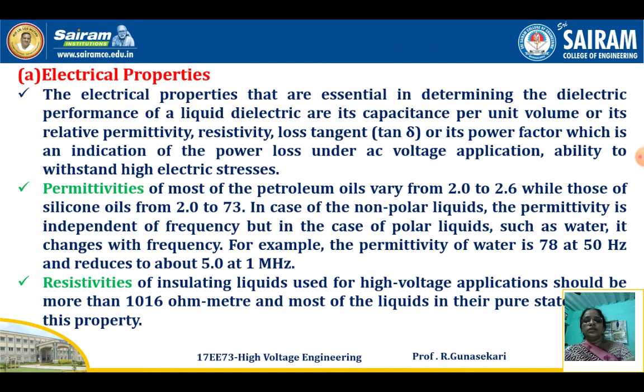Then resistivities. The resistivity of the insulating liquid dielectrics used for high voltage applications should be more than 10 to the power 16 ohm meter, and most of the liquids have this in their pure state only. Then power factor. The power factor of a liquid dielectric under AC voltage will determine its performance under loaded condition. The power factor is a measure of power loss and is an important parameter in cable and capacitor systems. The pure and dry transformer oil will have a very low power factor, varying between 10 to the power minus 4 at 20 degree centigrade and 10 to the power minus 3 at 90 degree centigrade at a frequency of 50 Hz.